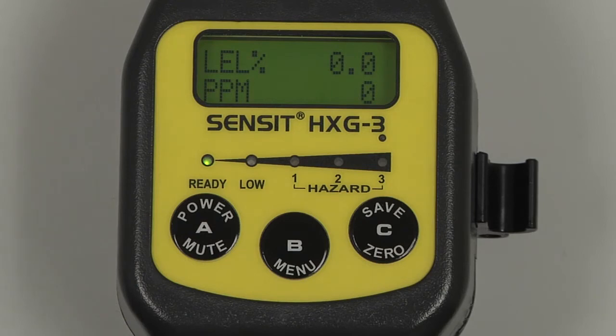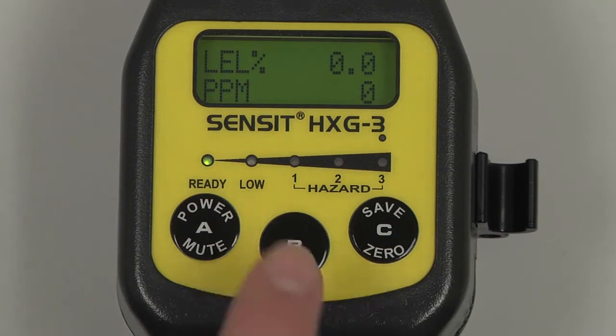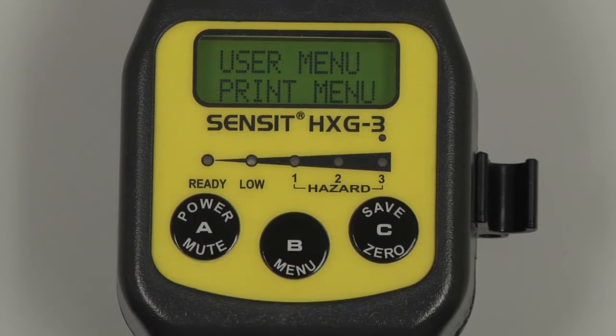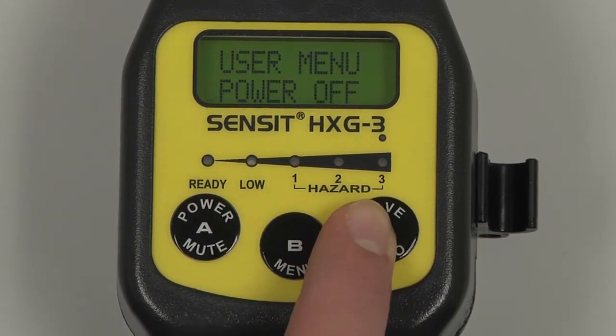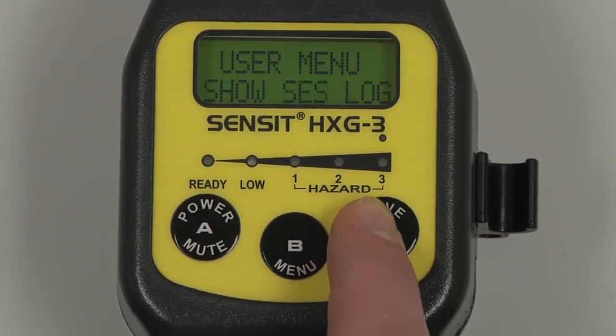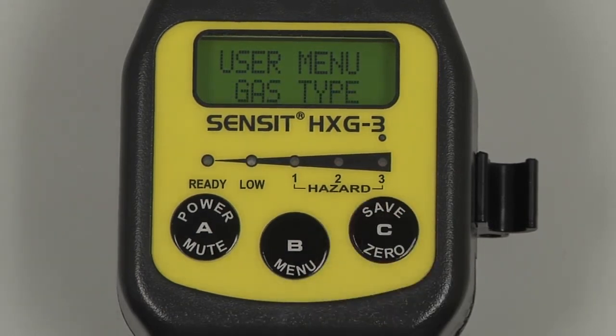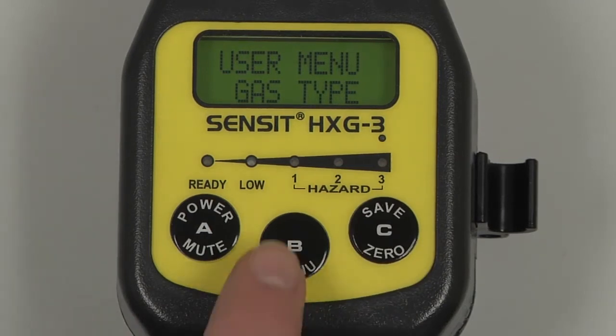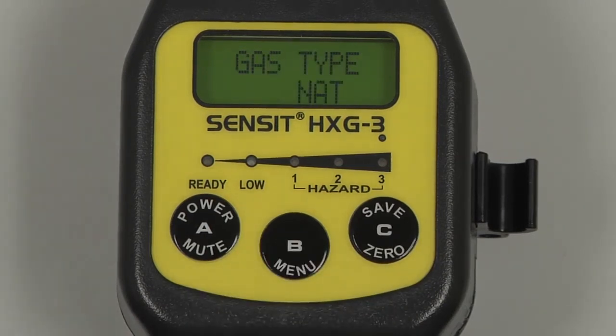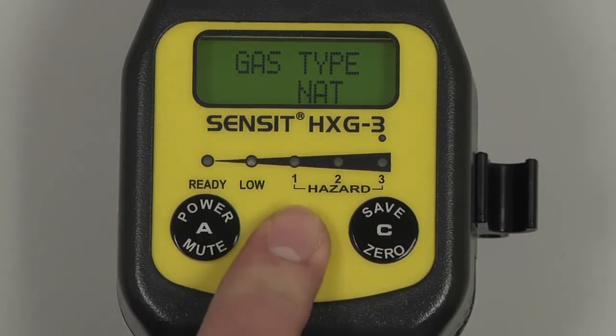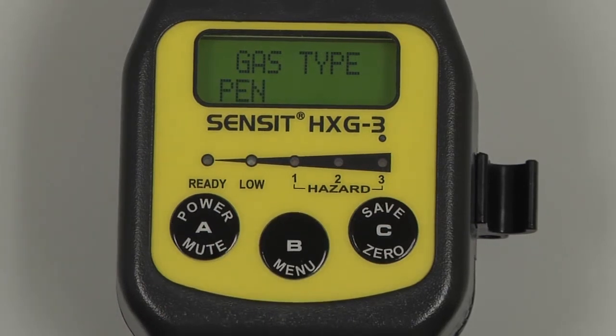For pentane, if the instrument is not already set up for pentane, we can change the gas type in the user menu. Press and hold the B button to access that menu, and scroll by pressing and releasing the C button until gas type appears. Select by pressing and releasing the B button. And if natural gas is already selected, we can change to pentane by pressing and releasing the B button. Exit by pressing and releasing the A button.